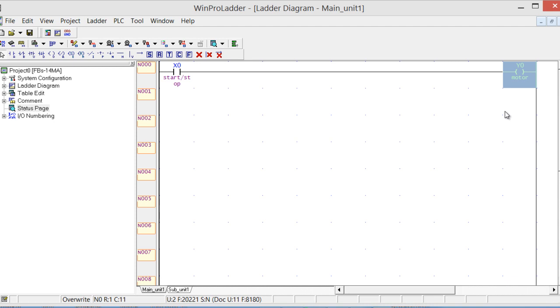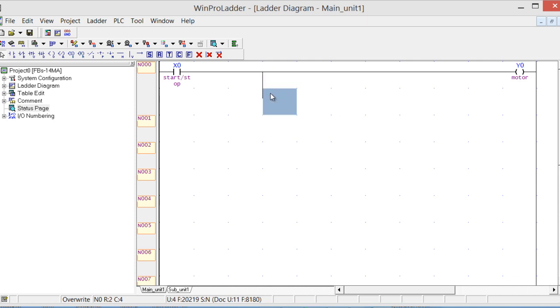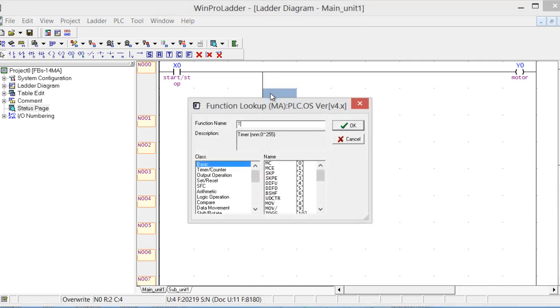This is the start-stop switch, and over here we assume that a motor is connected. It can be instead of motor, it can be anything, any machine. Click B on the keyboard to make a vertical branch line, click F and write T for timer. We'll be using T50 timer, and for now we will use 5 seconds. So 50 is equal to 5 seconds, that is 50 multiplied by 0.1 equals 5 seconds.